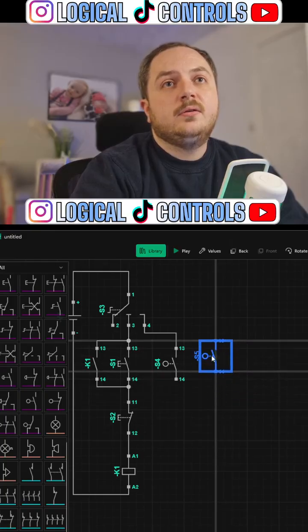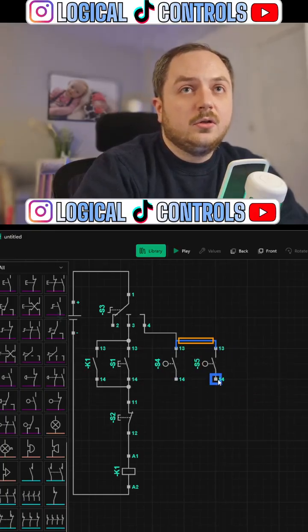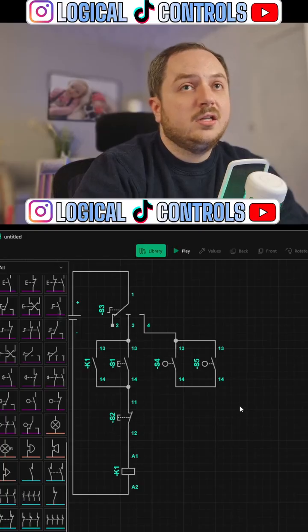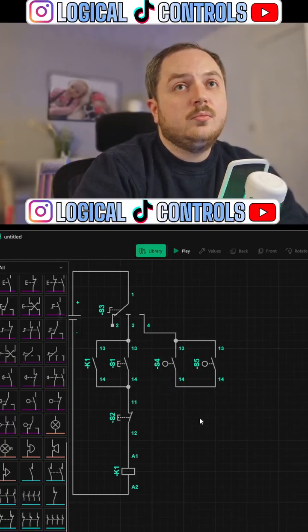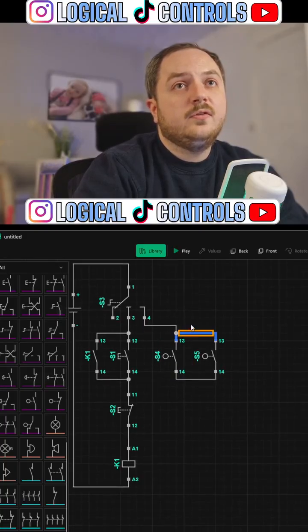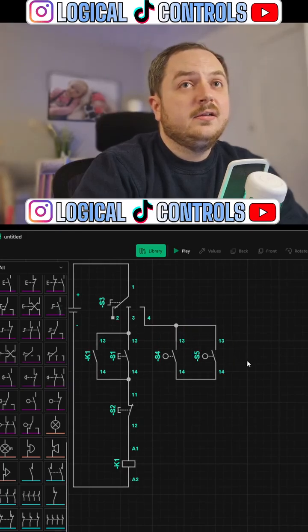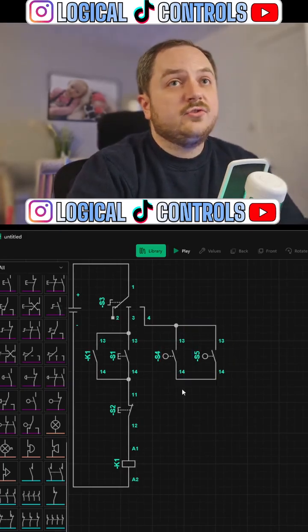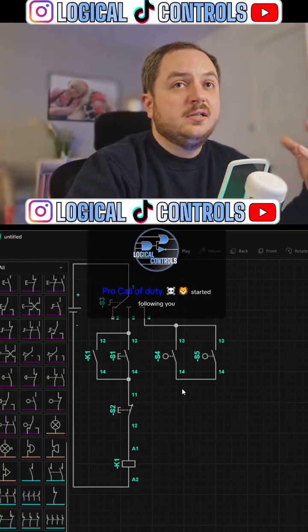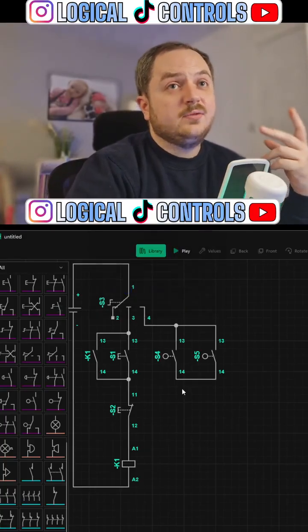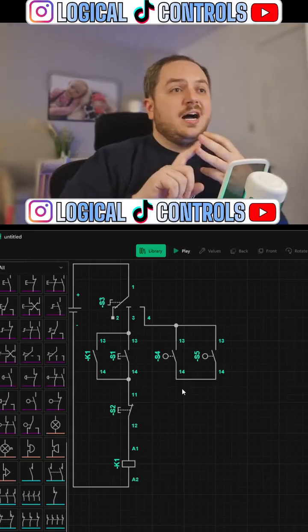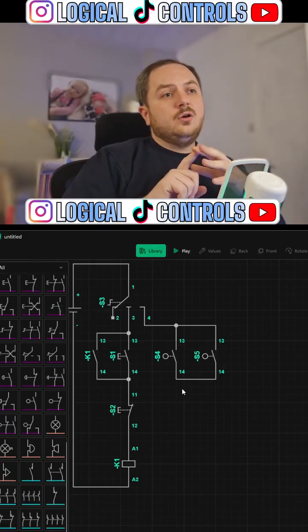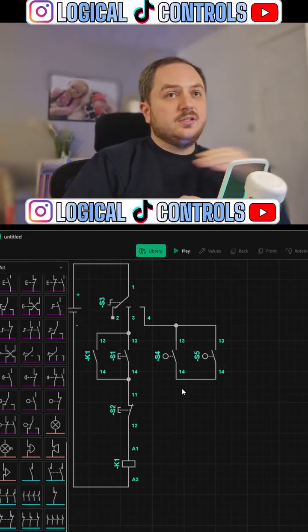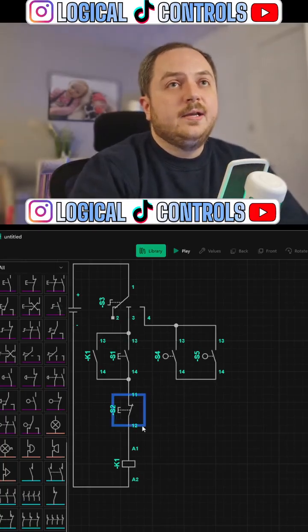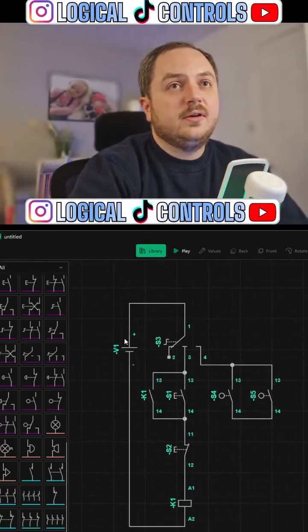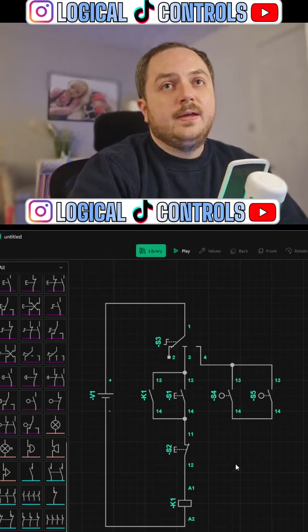So if either the low or the low-low is triggered, we want to start the pump. We want to stop the pump if the fuel level reaches high or high-high. That's how it's normally done, at least in the industry I work in. There's normally 4 switches: a low switch, a low-low switch, a high switch, and a high-high switch.